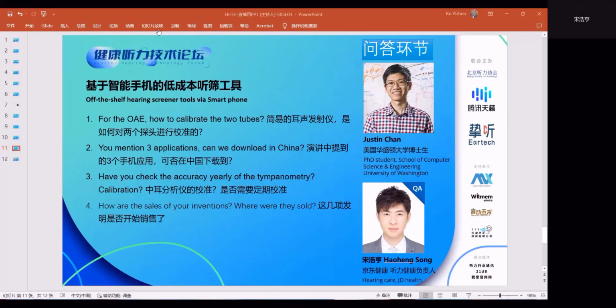Okay. The first one is about calibration for the otoacoustic emission. How to calibrate the two tubes? Right. So, as I'm sure a lot of you know, because you're all familiar with audiology, for OAEs, when you're sending those two tones, they need to be calibrated to a specific sound level. So typically, the first tone, F1, is calibrated to 65 dB SPL, and F2, the second tone, is calibrated to 55 dB SPL. So for that, we actually just use a regular sound level meter, and we have to do some manual calibration. So even if you fix the length of the silicon tubes to a fixed length, you still need to double check this calibration process.